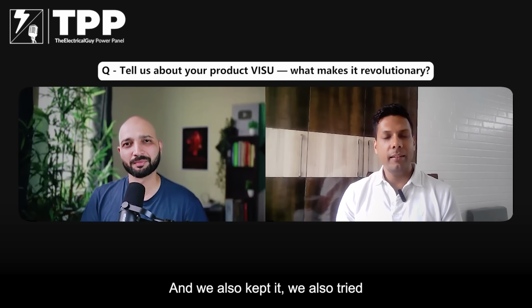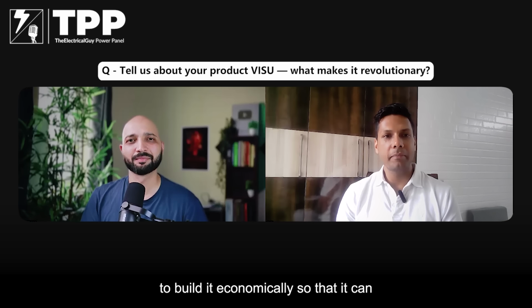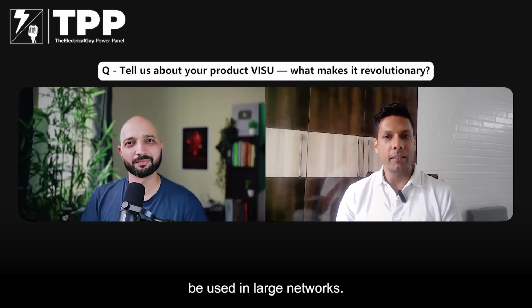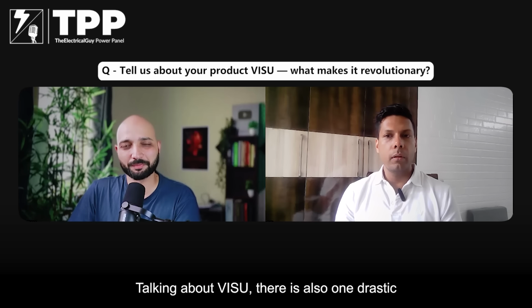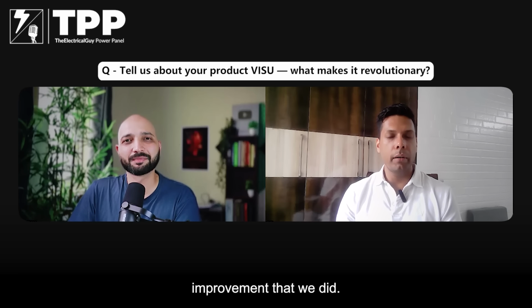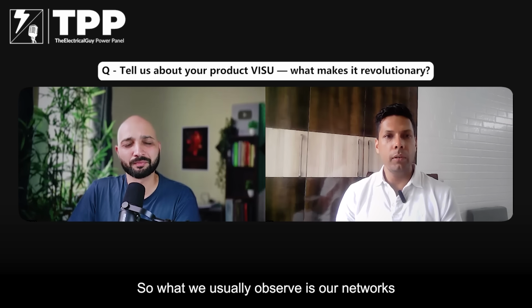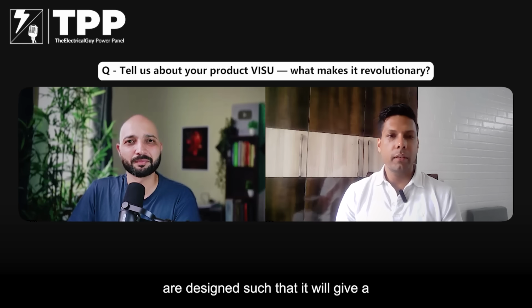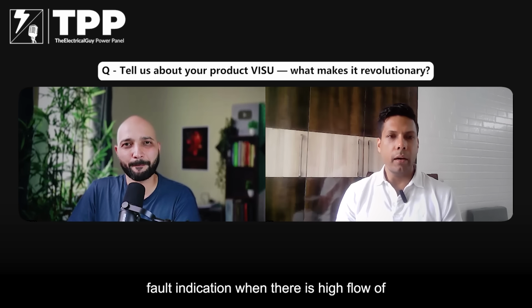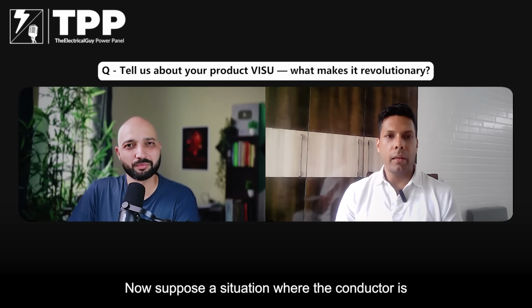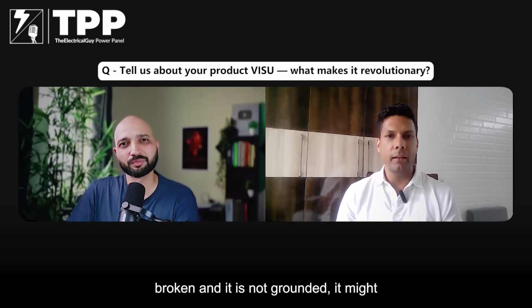And we also tried to build it economical so that it can be used in large networks. Talking about VISU, there is also one drastic improvement that we did. It is called the broken conductor. What we usually observe is our networks are designed such that they give a fault indication when there is high flow of current. Now suppose a situation where the conductor is broken and it is not grounded. It might be hanging on a tree or somewhere else.